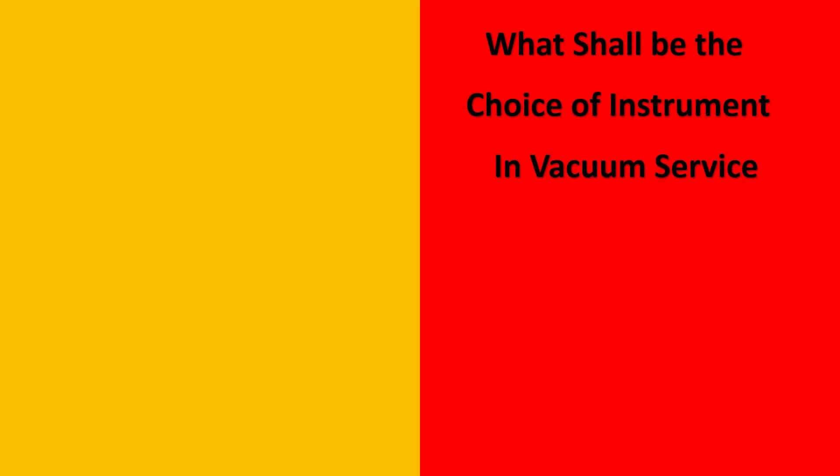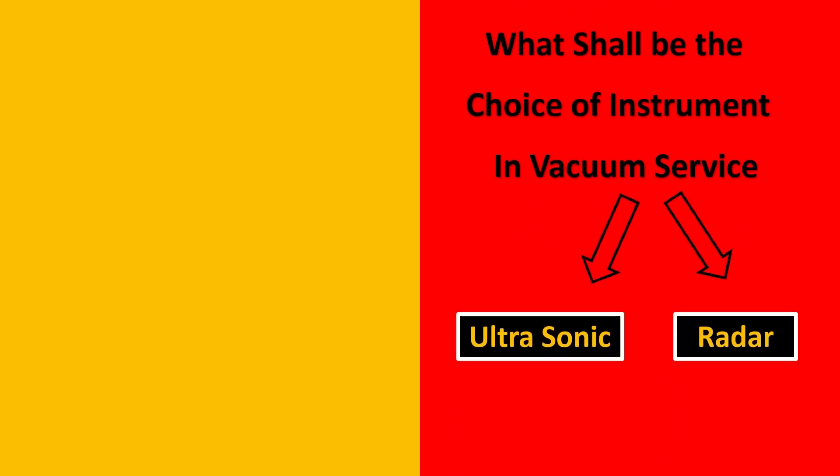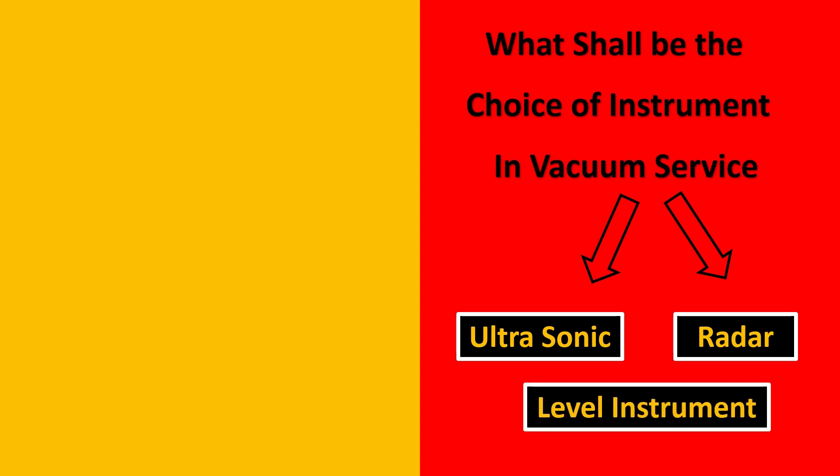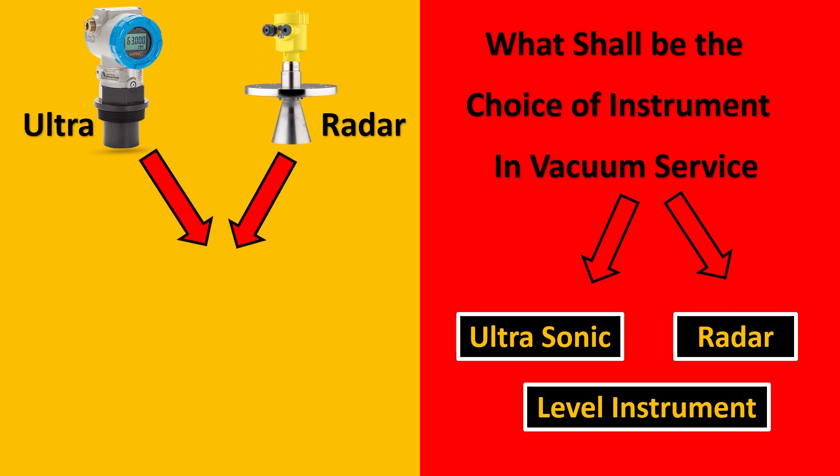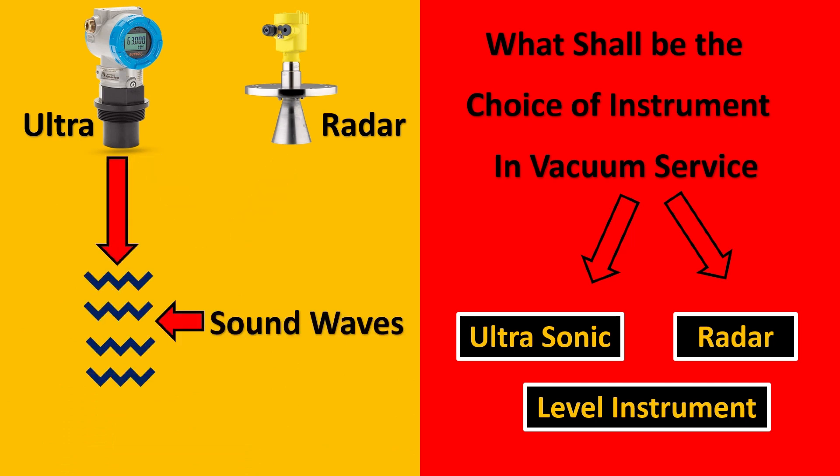Now the next question which is asked is what shall be the choice of instrument in vacuum service for measuring level? Will you go for ultrasonic or radar instrument? But and why is this the case? The answer is yes, both of these are amazing instruments. They use their waves to transfer and find out the level. But ultrasonic especially uses sound waves. And we all know that sound waves cannot travel in vacuum. Thus, our choice for vacuum services would be radar and not ultrasonic.